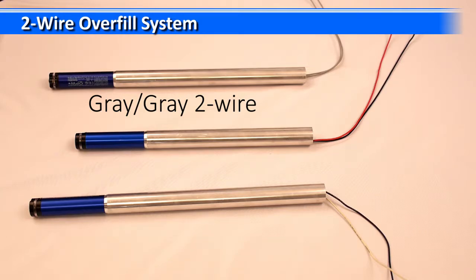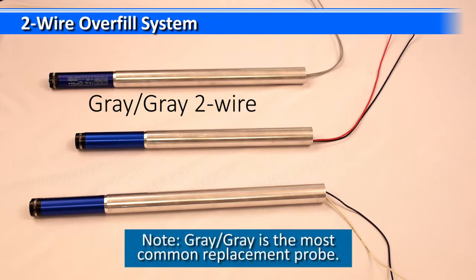Okay, the gray universal probe color wires, that's going to be the most flexible for you. If you're in the parts business or parts distributor, that style probe is going to replace 90% of the probes out there. Unless you're dealing with some older equipment, say pre-2000s, that gray probe should replace red-black and white-black in those applications.